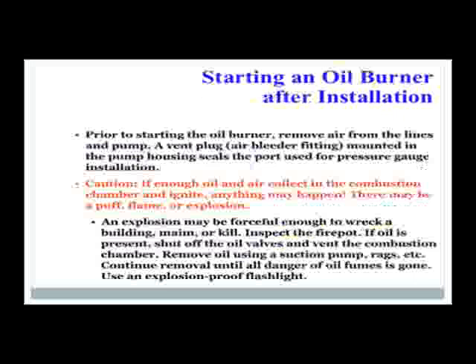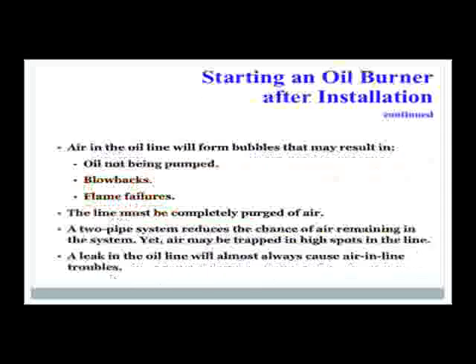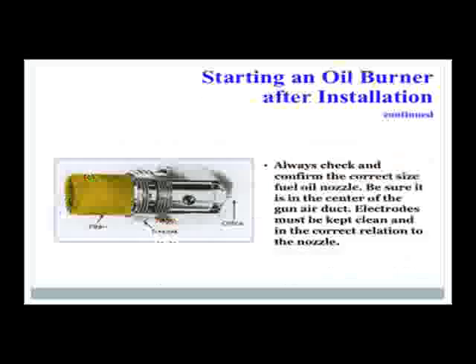Inspect the fire pot. If oil is present, shut off the oil valves and vent the combustion chamber. Remove the oil using a suction pump, rags, etc. Remove the oil until all danger of oil fumes is gone. Use an explosion-proof flashlight. Air in the oil line will form bubbles that may result in oil not being pumped, blowbacks, and flame failures. The line must be completely purged of air. A two-pipe system reduces the chance of air remaining in the system, yet air may be trapped in high spots in the line. A leak in the oil line will almost always cause air in line troubles. Always check and confirm the correct size of fuel oil nozzle. Be sure it is in the center of the gun air duct. Electrodes must be kept clean and in correct relation to the nozzle.